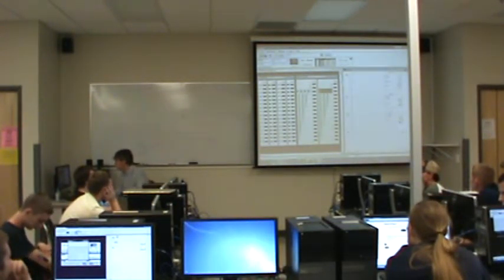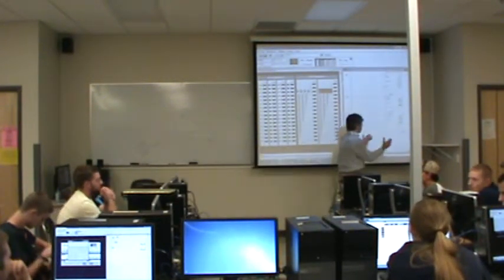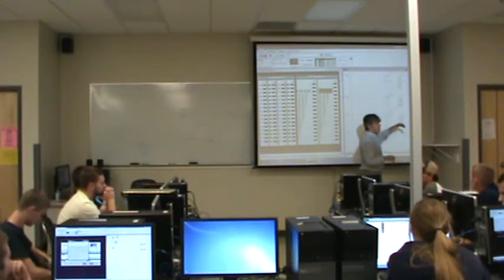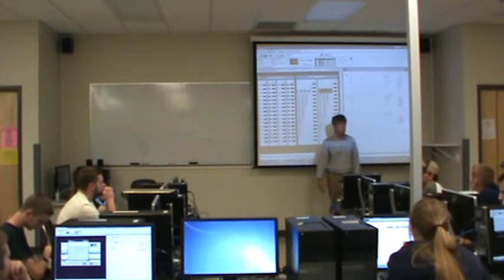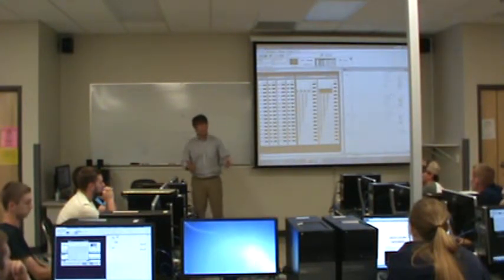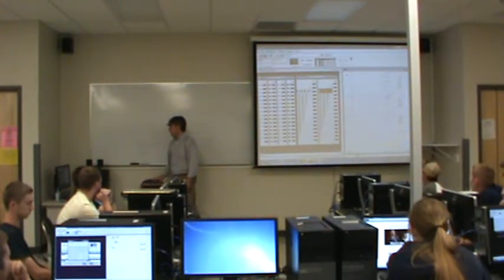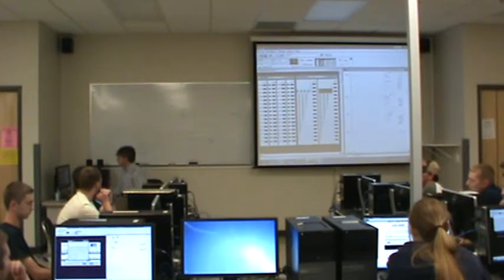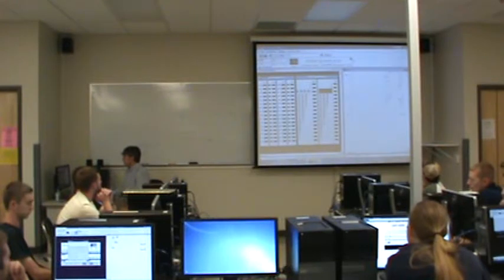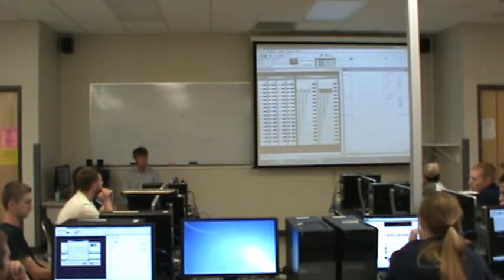But anyway, this should be a lesson to you. An output coil or anything that writes a whole word of data, whatever comes last is going to overwrite any calculations from before. So you have to be careful about that. I've already had 1 or 2 students say, hey, what's going on with my program? It's not working. And I was able to show them, well, you've got the same output on 2 different lines, which is a mistake. Basically, this line here with the move instruction is not doing anything really. It's just wasting scans. So now we get the same result. Okay. Any questions so far?